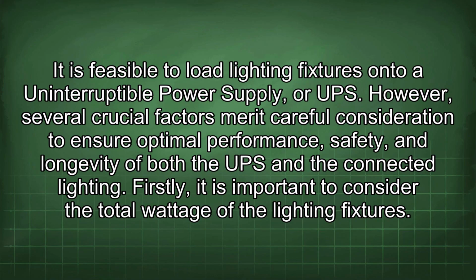It is feasible to load lighting fixtures onto an uninterruptible power supply, or UPS. However, several crucial factors merit careful consideration to ensure optimal performance, safety, and longevity of both the UPS and the connected lighting. Firstly, it is important to consider the total wattage of the lighting fixtures.